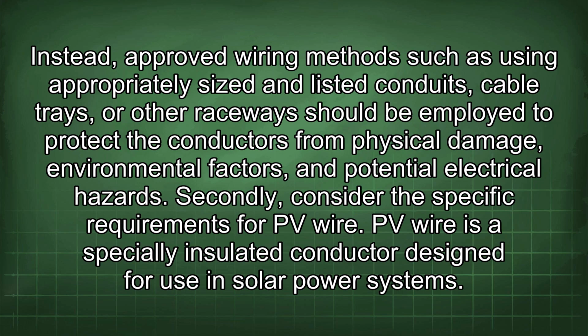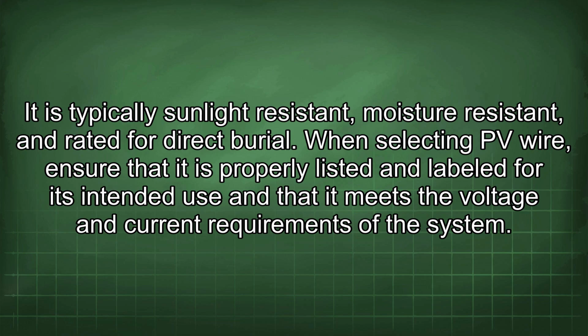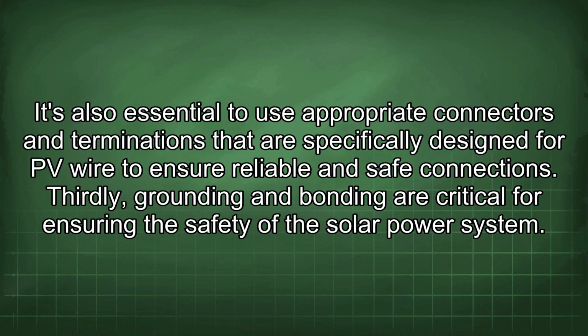Secondly, consider the specific requirements for PV wire. PV wire is a specially insulated conductor designed for use in solar power systems. It is typically sunlight resistant, moisture resistant, and rated for direct burial. When selecting PV wire, ensure that it is properly listed and labeled for its intended use and that it meets the voltage and current requirements of the system. It's also essential to use appropriate connectors and terminations that are specifically designed for PV wire to ensure reliable and safe connections.